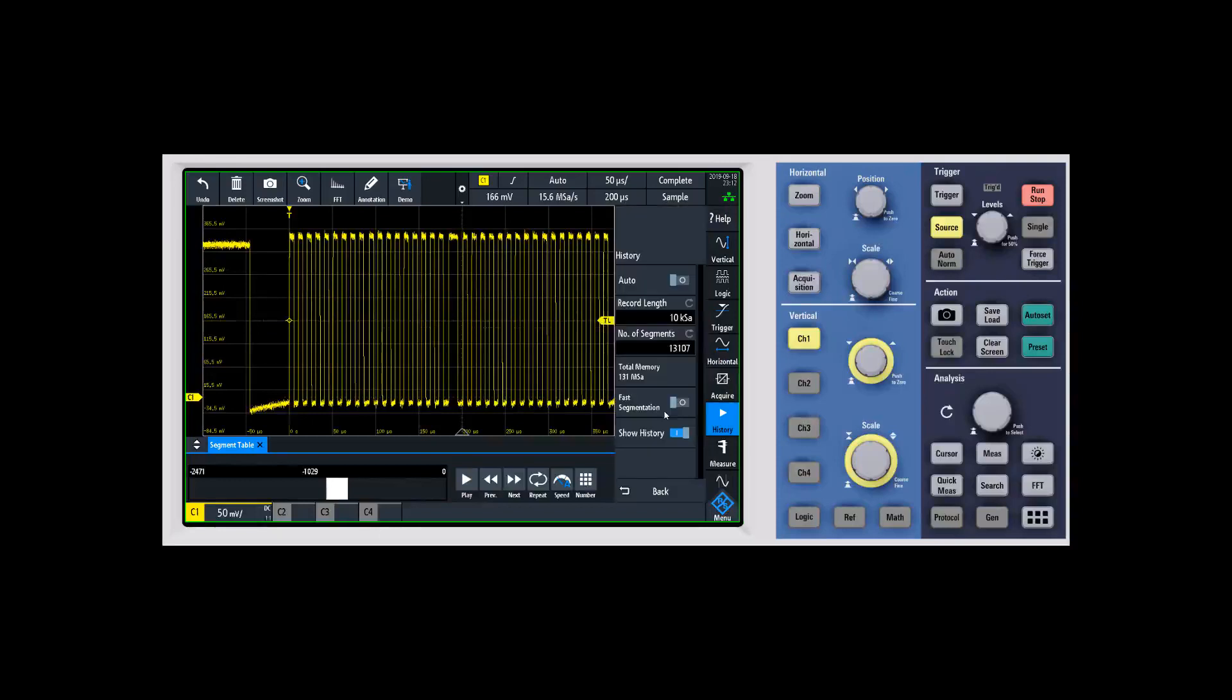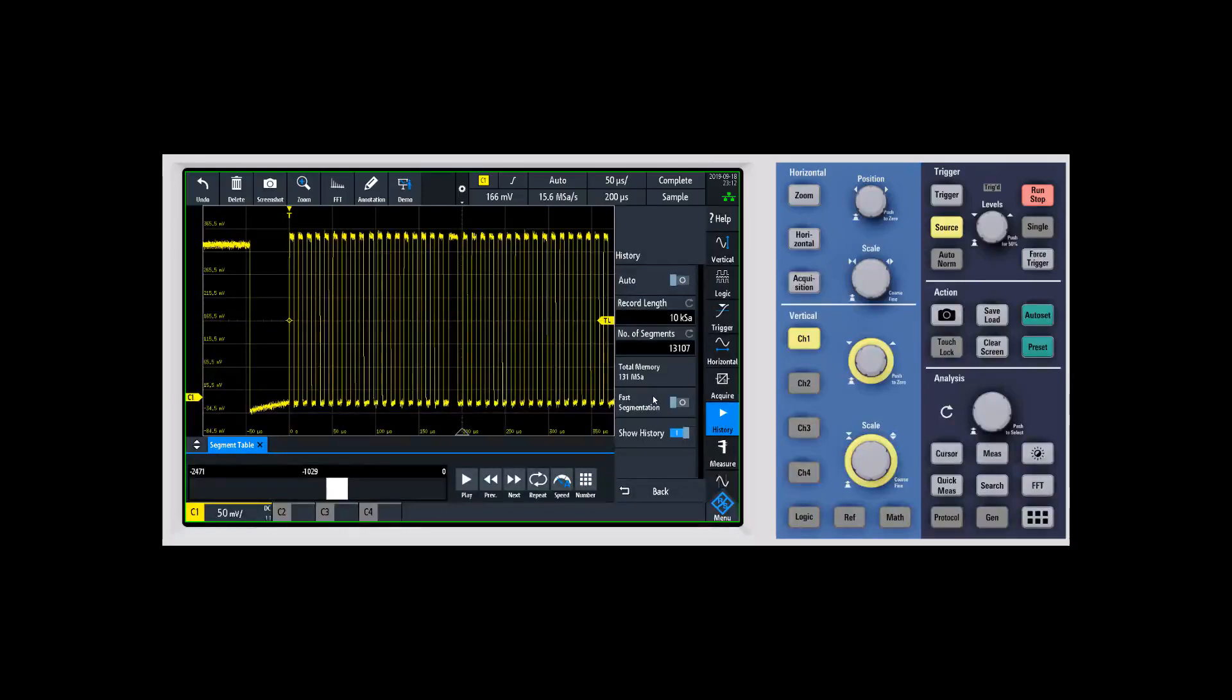There was one more thing you might have noticed when you go into history mode, and that is fast segmentation. Fast segmentation allows you to—history mode has a certain rearm time, and because history mode is always running in the background, that rearm time is going to include us displaying the waveforms to the actual display.